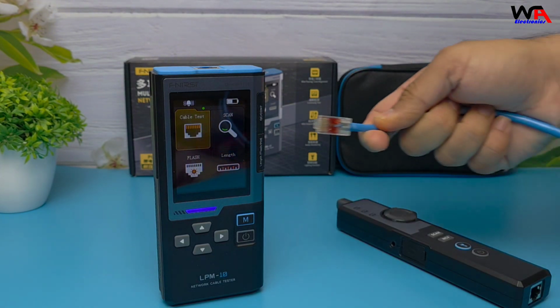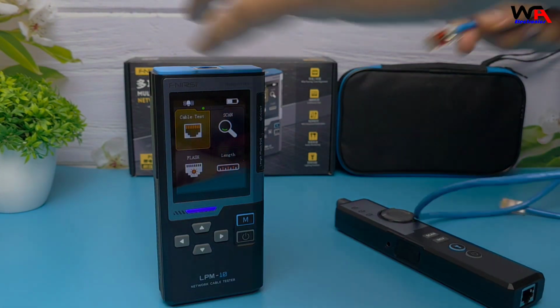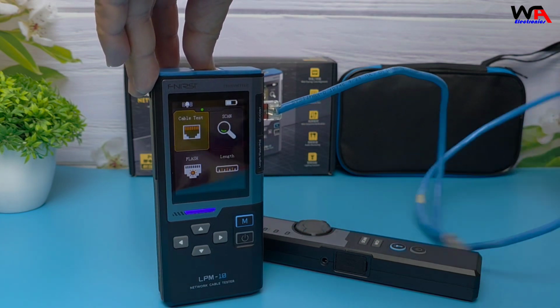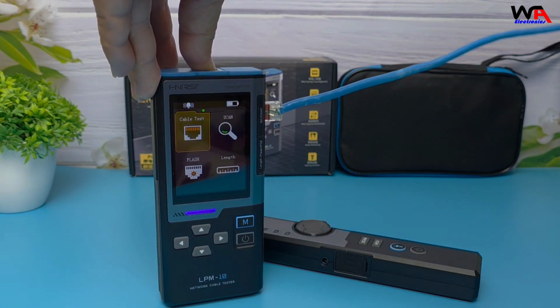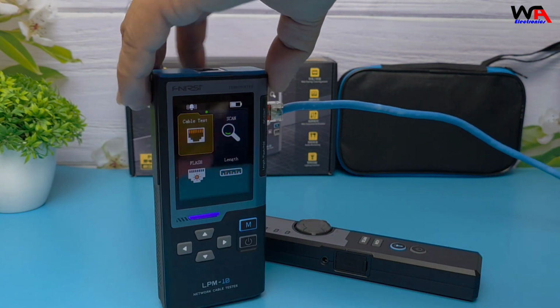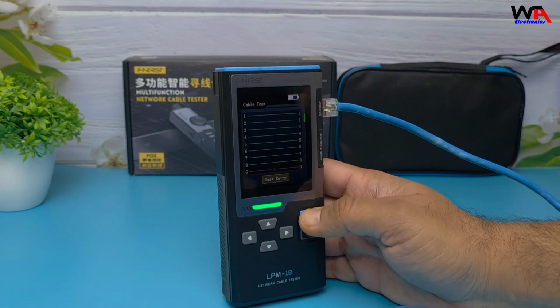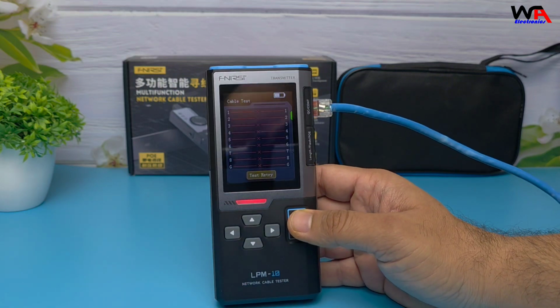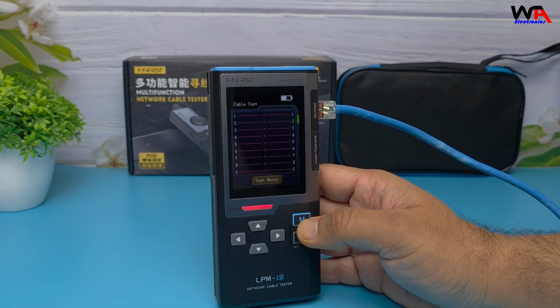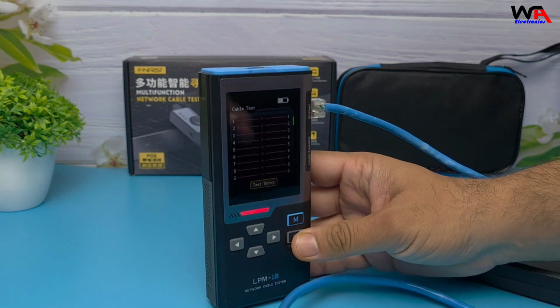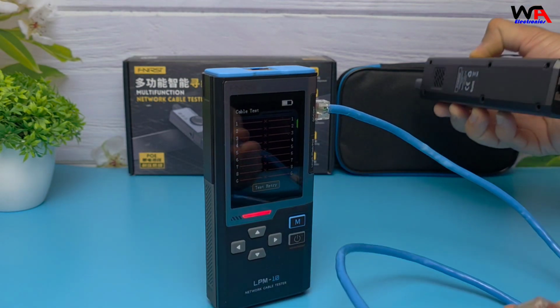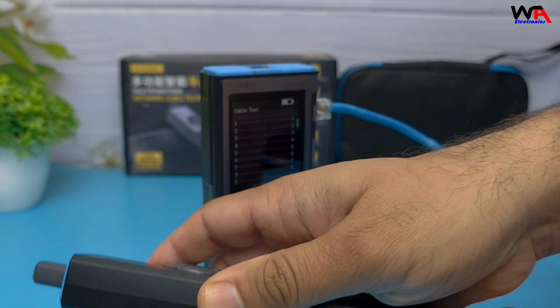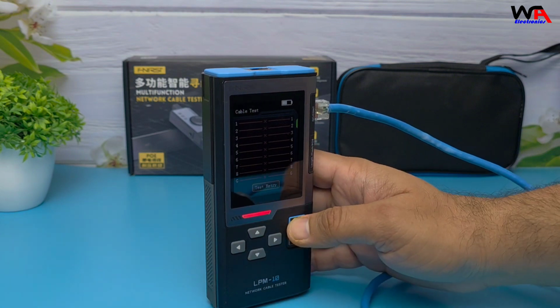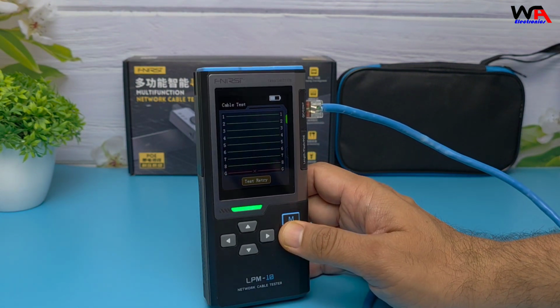Cable tracing. Let's start with cable tracing. Connect the transmitter to the cable using an RJ45 port or alligator clips. The receiver instantly picks up the tone. Normal mode is fast and works best in clean environments. Anti-interference mode shines in data centers or places with heavy electrical noise. You can also adjust sensitivity to pinpoint exact cables.